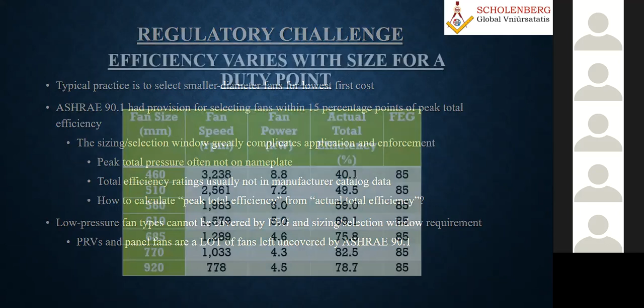Generally we go for a smaller diameter fan for the lowest first cost. But you should always provide for selecting fans within 15 percentage points of peak total efficiency. ASHRAE has very clearly regularized this. The sizing and selection window generally complicates application and enforcement, and as I told you, majority of the time we go for over-design. ASHRAE has given very clear guidelines on that.